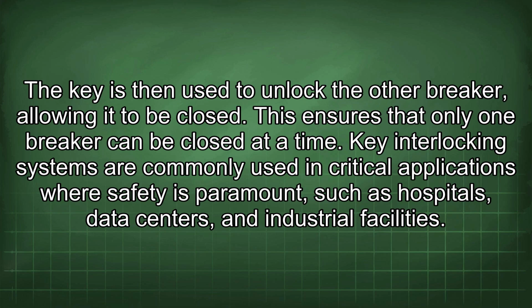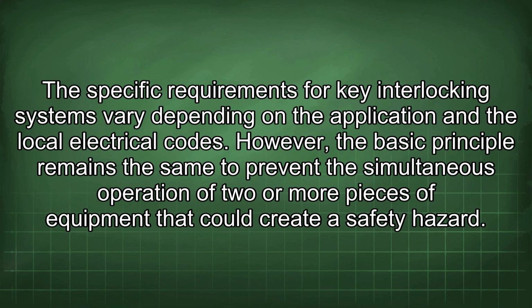Key interlocking systems are commonly used in critical applications where safety is paramount, such as hospitals, data centers, and industrial facilities. The specific requirements for key interlocking systems vary depending on the application and the local electrical codes. However, the basic principle remains the same: to prevent the simultaneous operation of two or more pieces of equipment that could create a safety hazard.